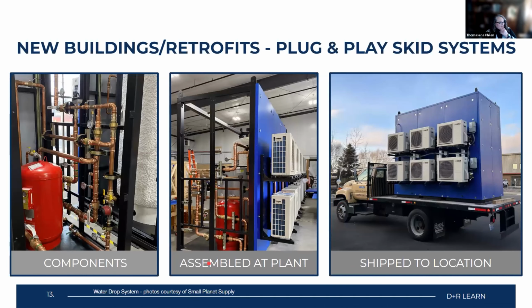Now, the neat thing is that not all buildings have the space to put that kind of storage, and not all buildings have the ability to retrofit into a heat pump water heating system seamlessly. So what the industry is doing is moving to a more modular, off-the-shelf type system. Now, these guys are the Sanco CO2 inverter-driven heat pumps, and they can be manifolded together to achieve whatever capacity is needed. They can be put on the skid.